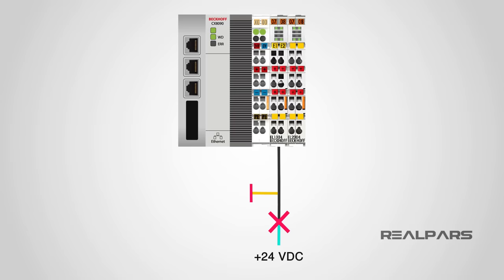You never want to put yourself in a situation like this. Because this is too late and also too dangerous. So what's the solution here? Well, let's repeat the same scenario, but this time, replace this normally open emergency stop switch with a normally closed switch.